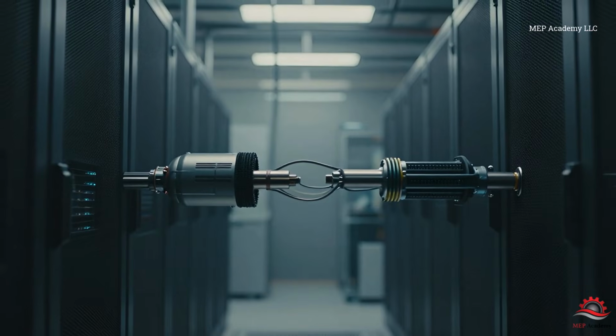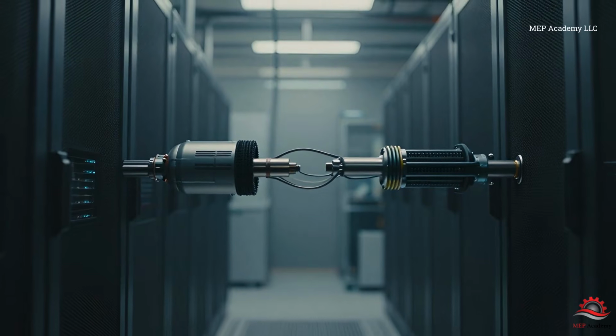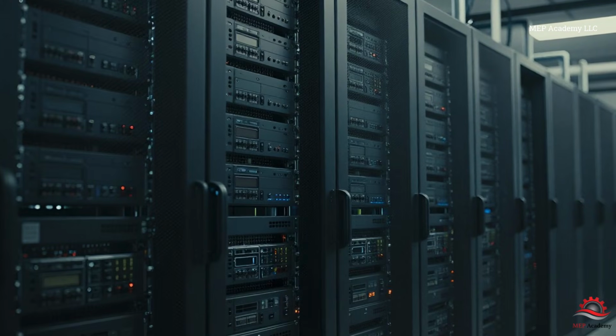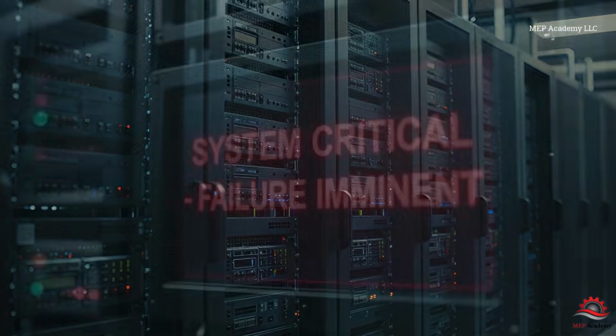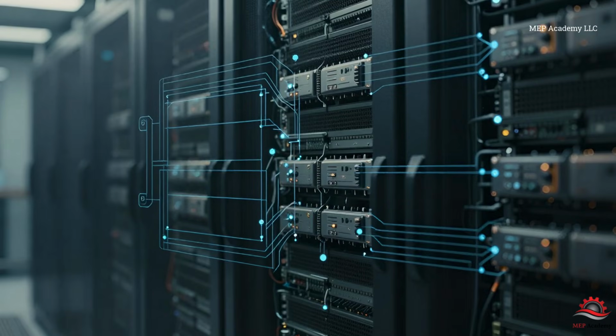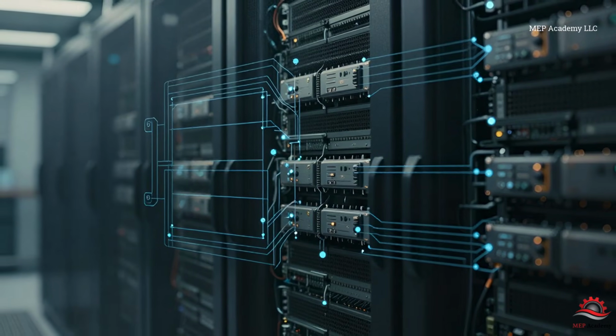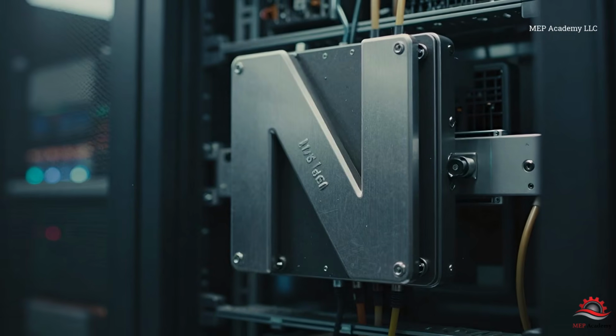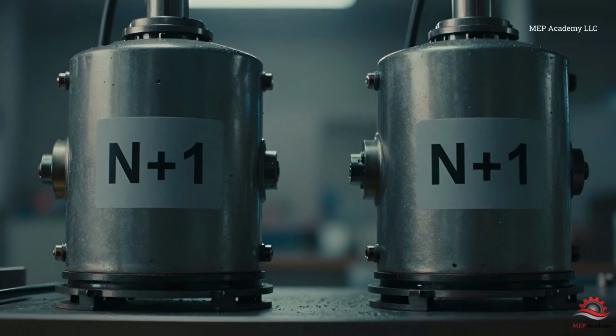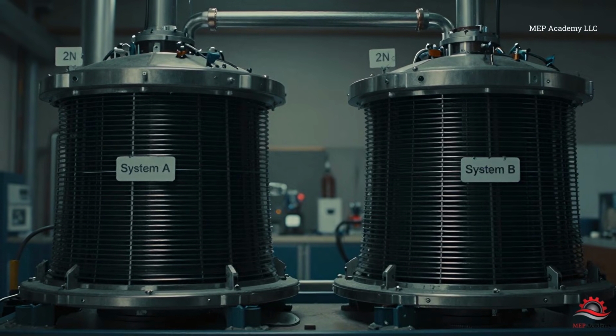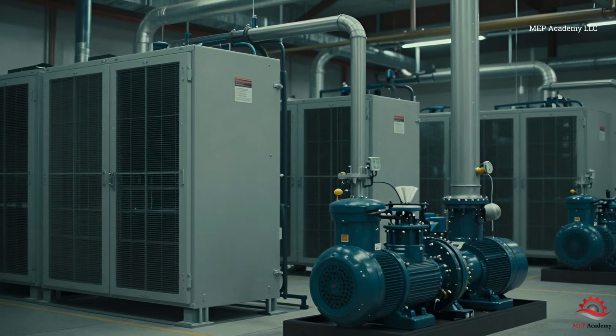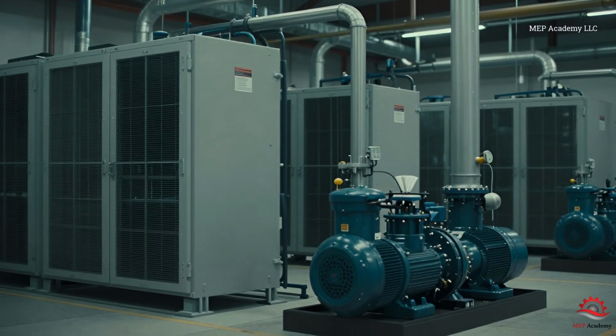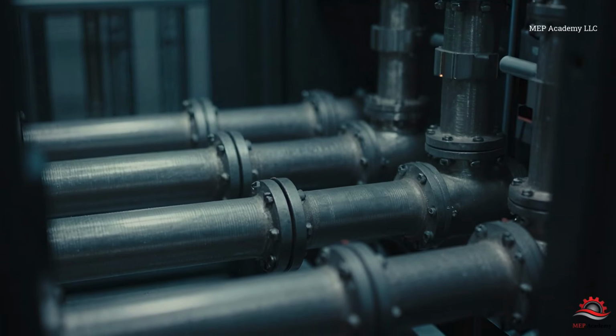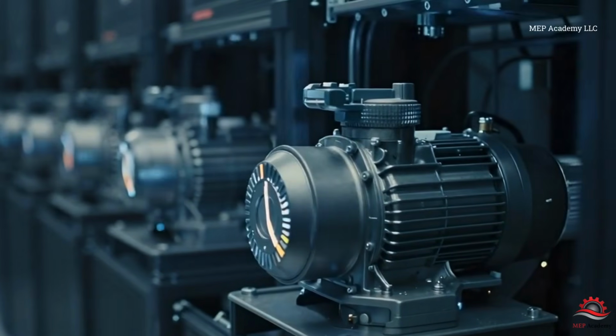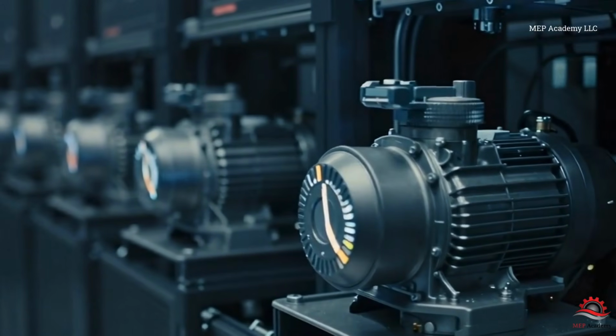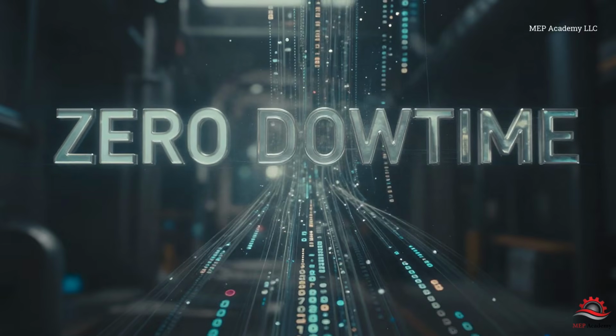Now let's connect this to what we discussed in the redundancy video. Cooling systems in data centers are designed just like power systems. They must never fail. That's why chilled water systems are designed with redundancy such as N systems, minimum required, N+1, one backup component, 2N, fully duplicated systems. You might have multiple chillers, backup pumps, and redundant piping loops. So if any single component fails, the system continues operating without interruption, because downtime is not an option.